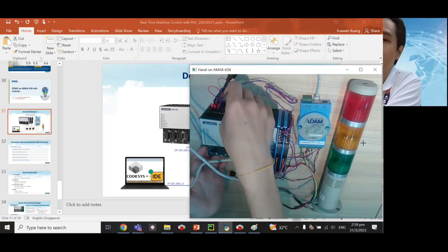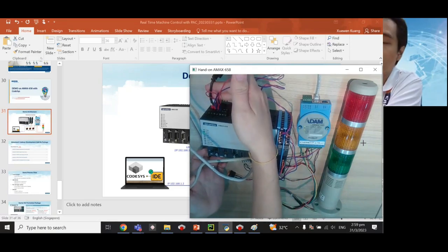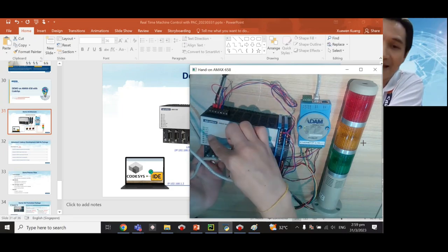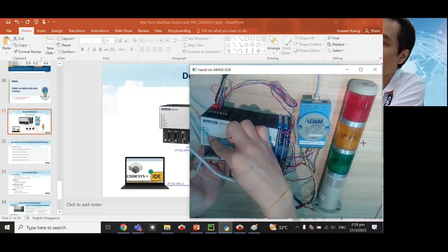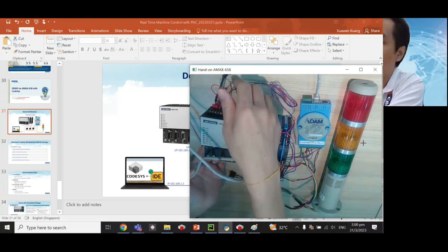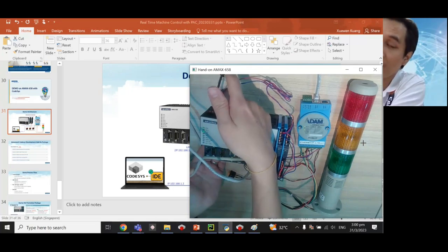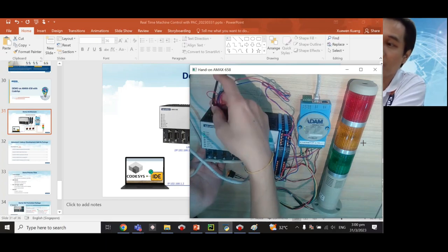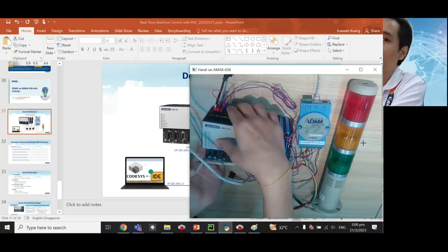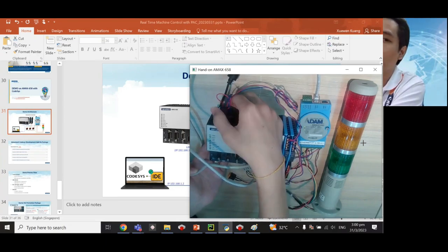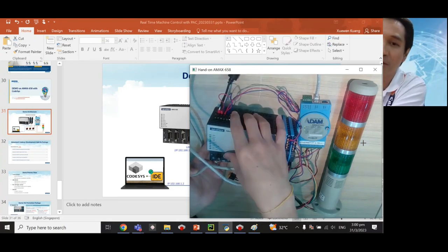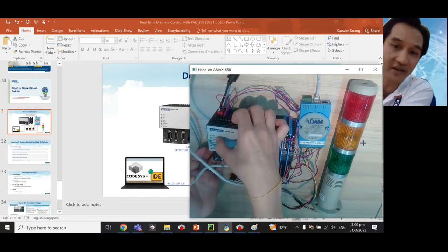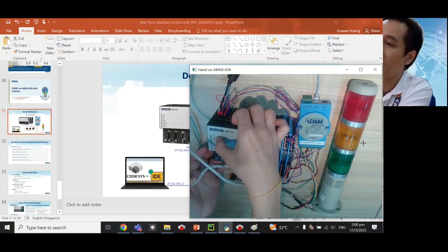This hardware supports dual power, so redundant power will be there. If you see that this ERR LED is on, it means that one of your power supplies has an issue. Their design is redundant power, so you have to supply power one and power two. You will see two power inputs here. I'm shorting these two cables, so I'm giving the same power to both power supplies. That's the reason you don't see the ERR LED on.